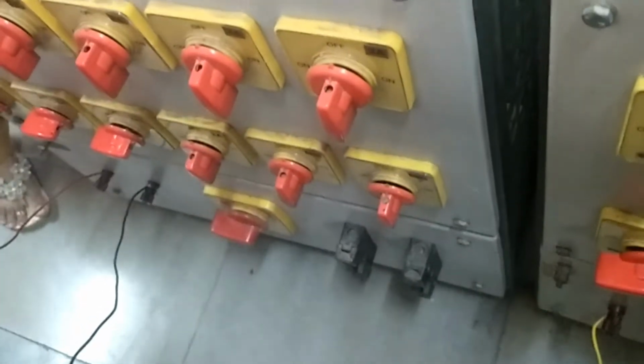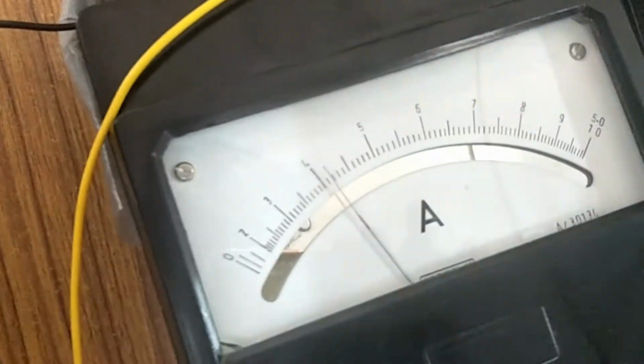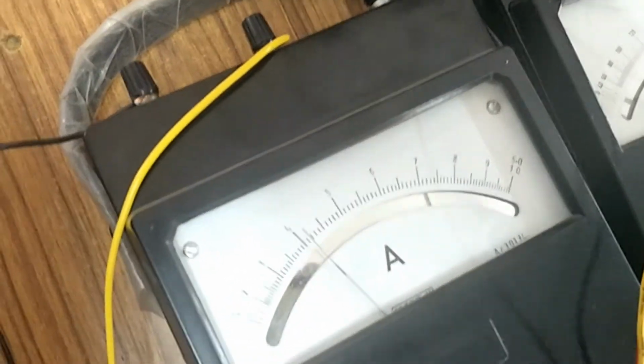Similarly, go for another load, turn on another load, and see that in both the cases the ammeters, see here, the teaser transformer secondary side ammeter is 4 amperes, and the main transformer secondary side is also almost 4.1. Both are almost the same. You can take 4.1 amperes now. Clear? And also the voltage rating 241, 241. And coming to the primary side, I1 reading 2.7, I2 reading 2.9, I3 reading 2.6 amperes, and W1 rating 135, and W2 130. So like that, for balanced readings you have to take and you have to tabulate as shown here.